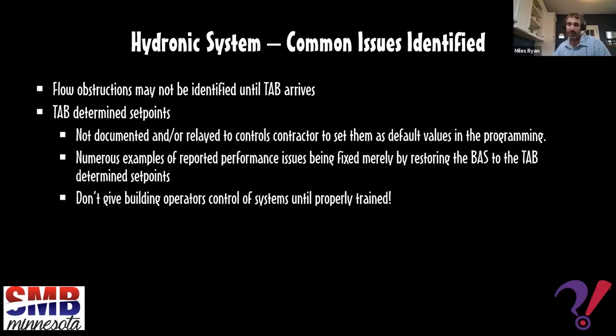We had nothing to work with because the previous control system went blank. It was completely dark. We couldn't find any TAB reports, and bringing in TAB wasn't within our scope for this project. Luckily, our firm had done a retro-commissioning in this facility 7 years prior, and we had screenshots on our computers that showed what the appropriate set point should be. So it was actually a fairly quick fix. Once we figured out the appropriate set point and put it in, the pump sped up, dehumidification started to happen, and as far as I know, it's not been an issue ever since.